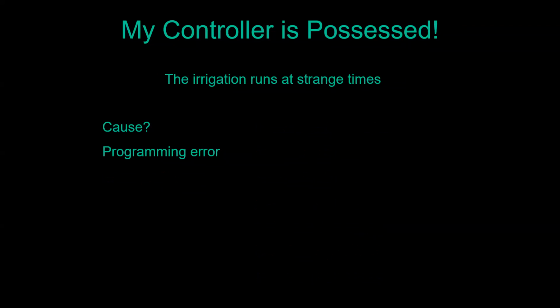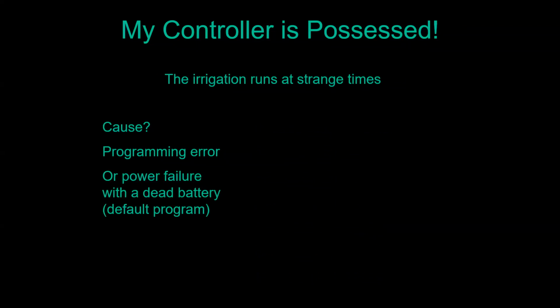If it just comes on at some weird random time, more than likely what happened is there was a power failure and you didn't replace your backup battery when you should have, and now the controller is running what's called the factory default program. All of your manufacturers that have the types of controllers that need that backup battery will always put in a default program in the A or number 1 program, and they set it to water every day, all stations for 10 minutes with 1 cycle, and they'll usually put in like a 5 or 7 a.m. start time for that default. But when the power comes back to the controller, it thinks it's midnight. So 5 or 7 hours later is when your sprinklers come on. So what you want to do at that point is go ahead and reprogram your timer and then make sure you put in a new backup battery.